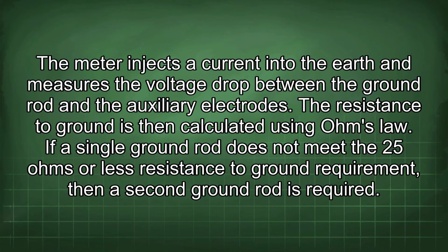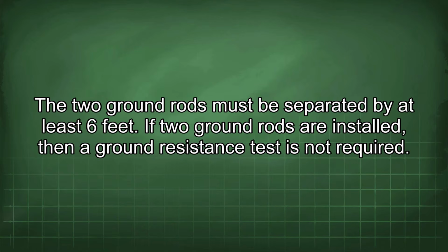If a single ground rod does not meet the 25 ohms or less resistance to ground requirement, then a second ground rod is required. The 2 ground rods must be separated by at least 6 feet. If 2 ground rods are installed, then a ground resistance test is not required.